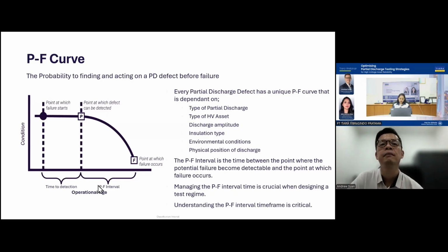Let me quickly go through how you operate this P to F curve. This point is where failure starts, but when a failure starts, it can be so small that your instrument can't even detect it at the moment, because the PD may be very small, just starting. The transient earth voltage and the ultrasonic sound caused by PD is so small that it can't be picked up, or sometimes it's even masked by noise. So this is the point where failure starts, but the time to detection will take time - sometimes months, sometimes weeks - until the instrument is able to pick up the signal from the PD.